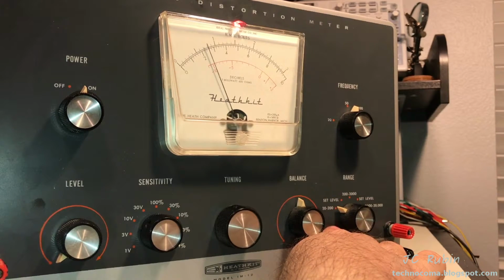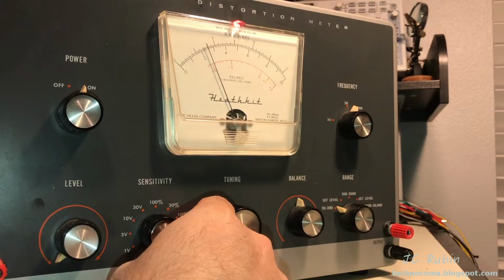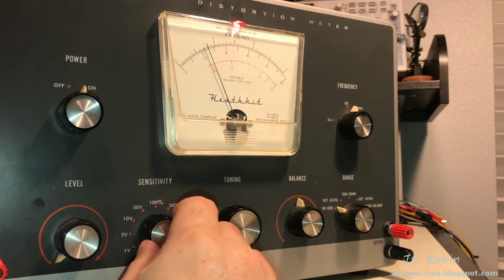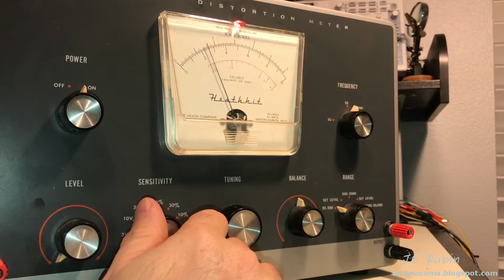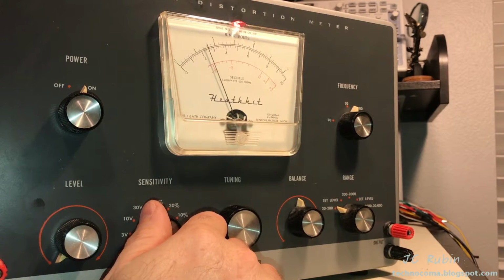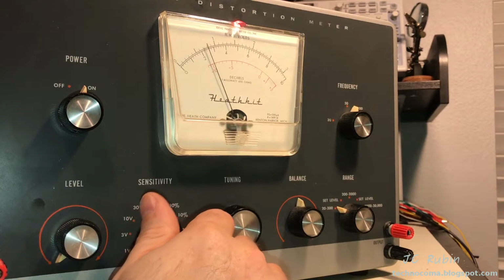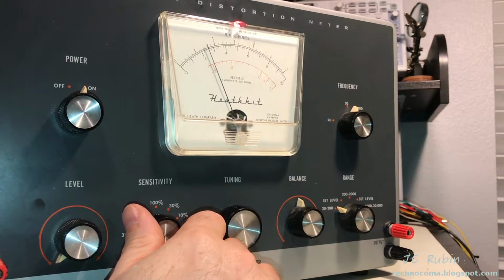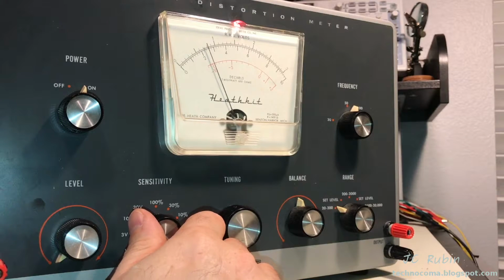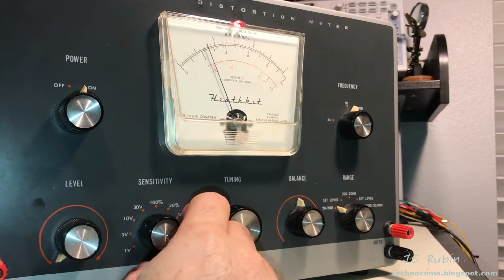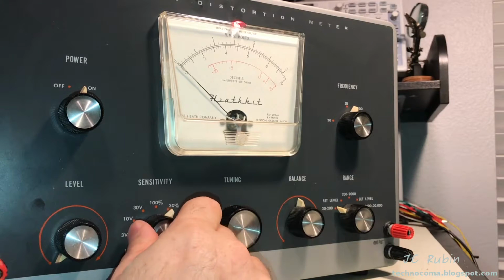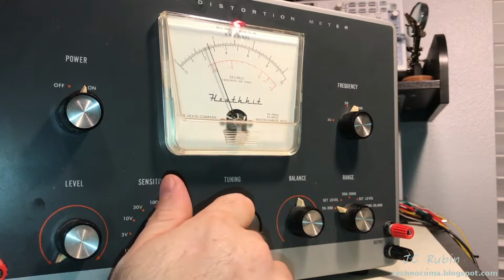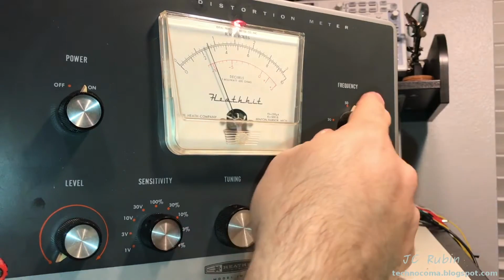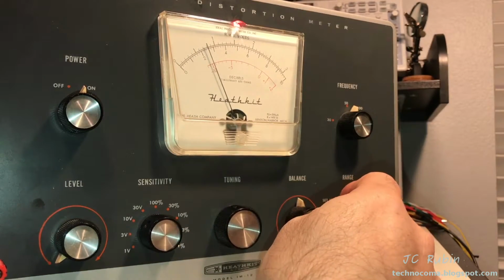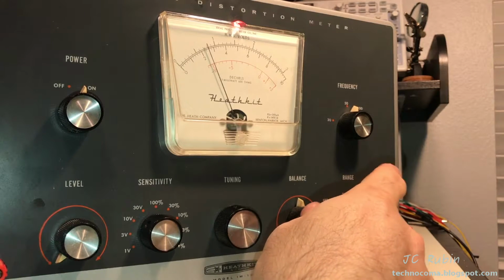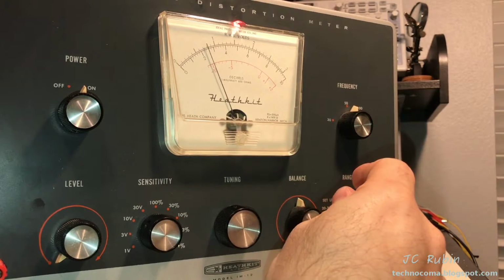2200, the lowest position. This sensitivity, I'll admit, they talk about bringing it right down to 1%. I don't encourage this. I think that once you figure out what you're doing, you could drill this down to 1% because you could screw this process up as much as you'd like and nothing really is going to happen. But as you feel more comfortable doing this, you could start drilling this down from perhaps 30 to 10 to whatever, right? And now that this knob is calibrated, you want to bring it to 60 hertz or in and around 50 for the purpose of the accuracy of this knob.